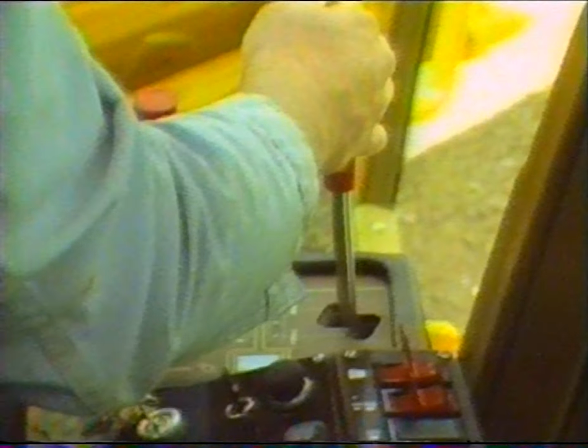One of the first things you will notice about the 8400 is the digital display on the controller. When you turn the ignition key to the on position, the 8400 uses the display to introduce itself with a set of 3 codes we call the startup sequence. The first code you will see are the letters CH. This, of course, stands for Champion. Next, you will see an issue number, like 1.7. This number identifies your controller if it should ever need service. Finally, the controller will show the number 8.8 as a way to test all the elements in the display.